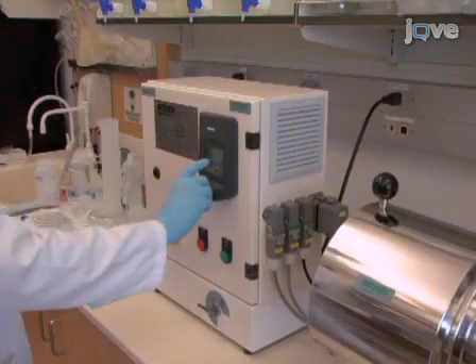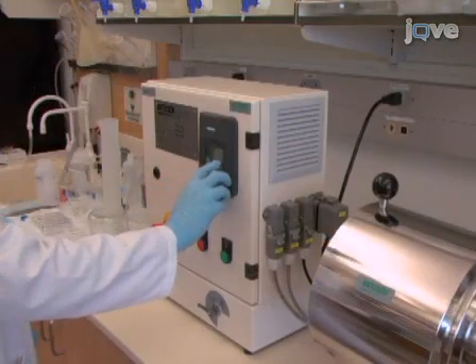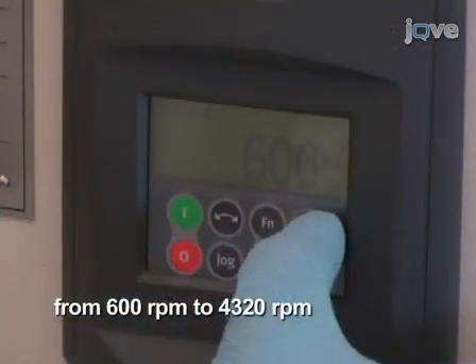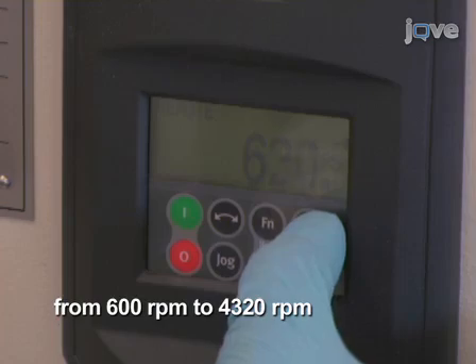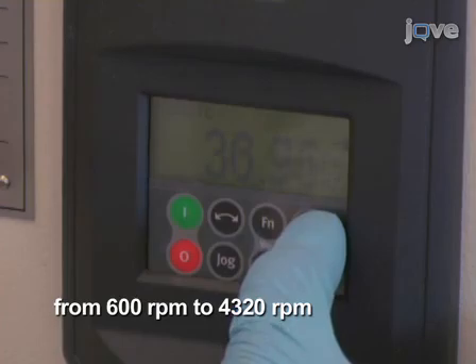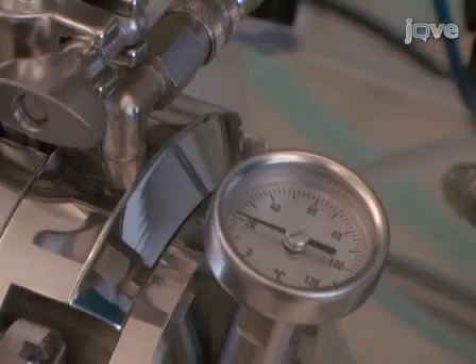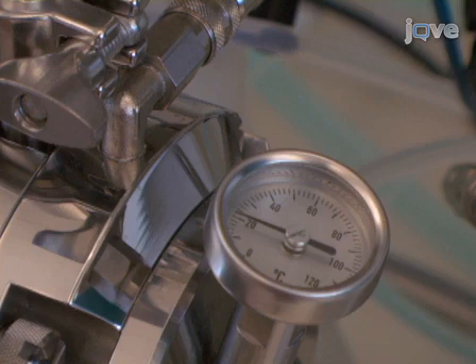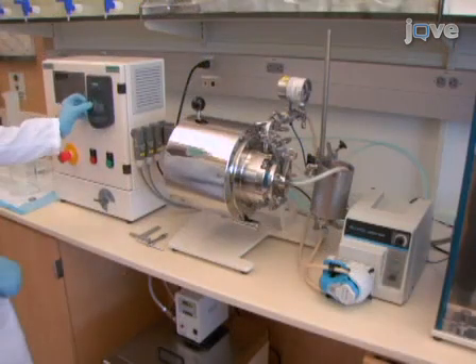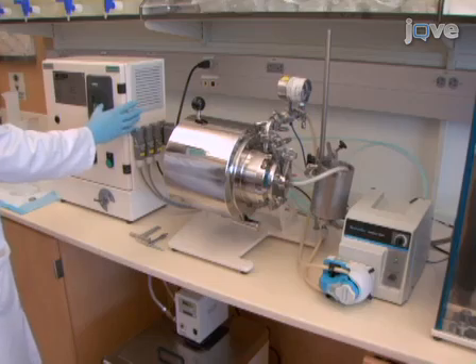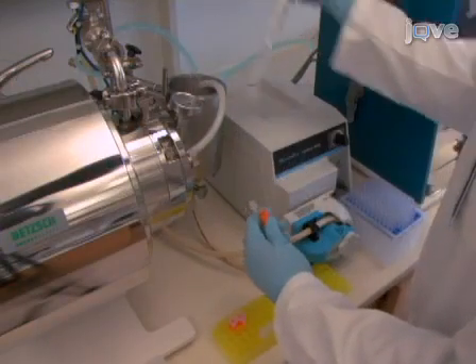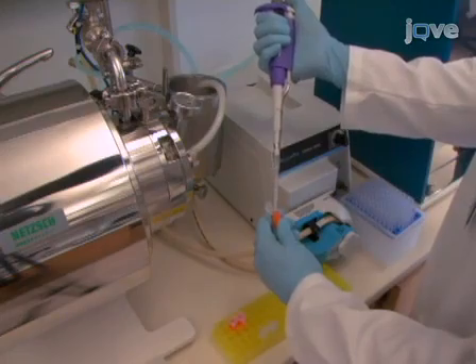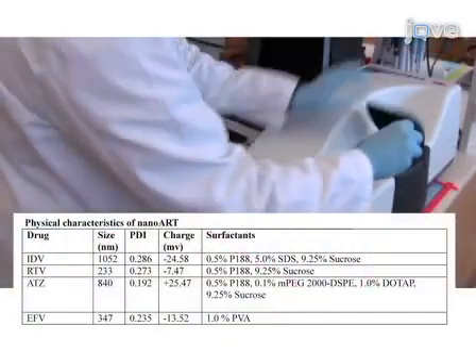Then, turn on the agitator and adjust the speed on the control unit. The speed can be increased from 600 rotations per minute to 4,320 rotations per minute on a MicroCer. Monitor the temperature using the temperature gauge that is attached on top of the grinding chamber to make sure that there is no overheating. Now mill the sample at various speeds and flow rates and take out small aliquots of about 1 milliliter of the formulation for size and charge measurements using a dynamic light scattering Malvern Zetasizer.